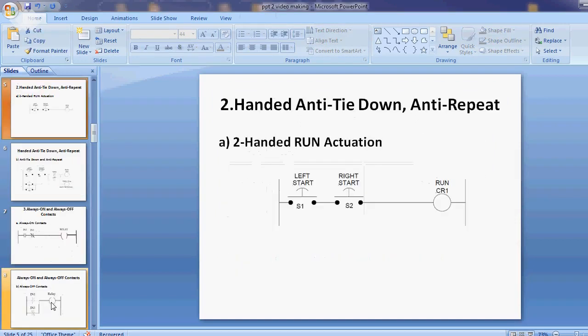Now we move to the next circuit discussing different circuits: two-handed, anti-tie down, and anti-repeat. First we discuss two-handed run activation — when the machine will be started by two switches, left start and right start. When both switches are ON, then and only then the run coil relay CR is ON, meaning the machine will be ON. Two switches are used because the machine is heavy, so the chances of accidental operation exist. The operator must confirm the operation by pressing both left and right switches simultaneously.